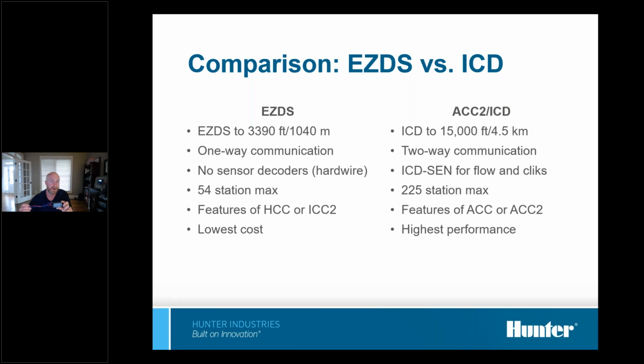It's only about 3,400 feet, and that's with 12-gauge wire. Like I said, it's one-way communication, and it's really not even communication. It's basically just an on-off. You can't do sensor decoders. Max station count's 54. You get all the features of an HCC or ICC2, and it is the lowest cost.